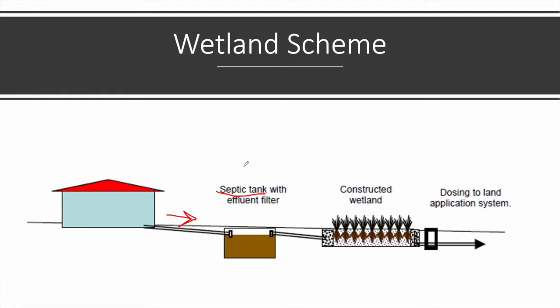It is very important to have a well-designed primary treatment because the constructed wetland, as a secondary treatment process, requires very low total suspended solids (TSS) and very low FOG (fat, oil, and grease). These two components can easily clog the wetland, potentially causing flooding. After secondary treatment, the wastewater can be further treated or safely disposed.